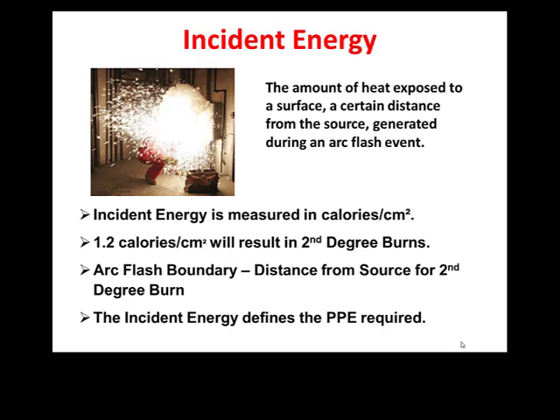For most office environments, 120 volts is primarily used, with 208 or 240 volts used for lighting and some types of equipment. Again, for voltages greater than 120 volts up to 240 volts, there is an arc flash hazard potential, but it is very unlikely since there probably is not enough energy to sustain the arc. An arc flash incident energy analysis would be required to determine the actual incident energy available for each electrical power distribution device.